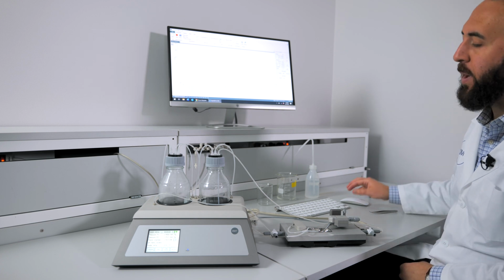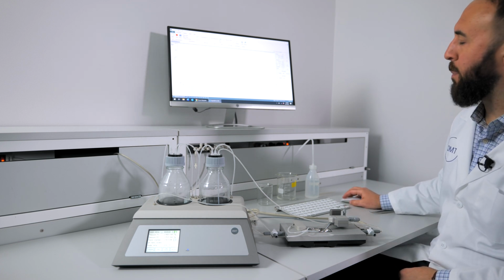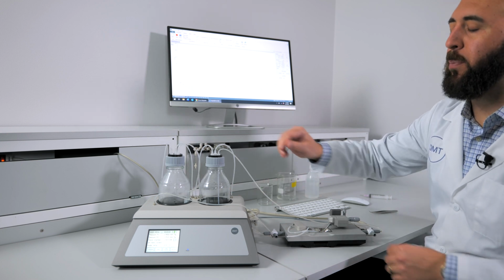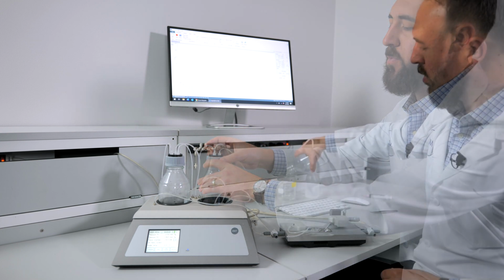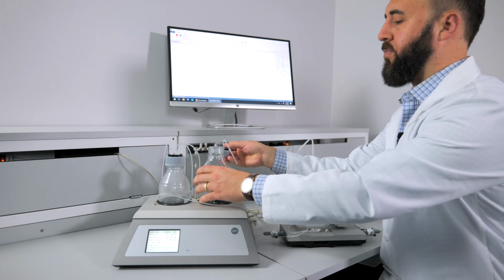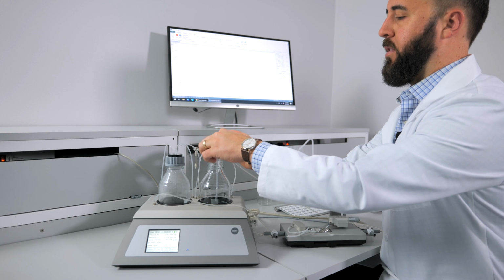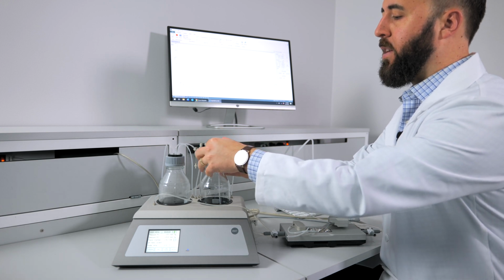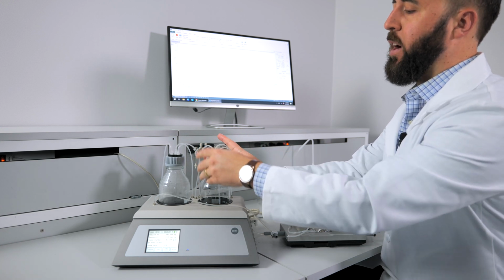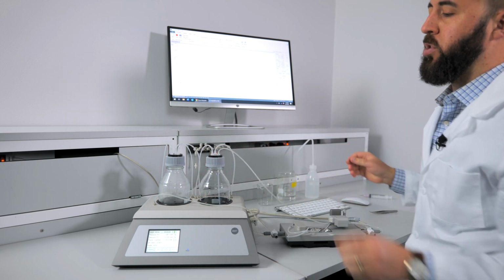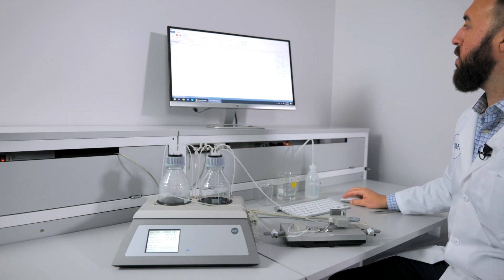After 15 or 20 minutes have passed, you can stop the pressure and empty the P1 bottle of the distilled water. You can reattach the bottle with nothing in it and we will repeat the process of pushing air through the lines to ensure that no buffer or water remains in the lines. Turn on pressure and make sure it reaches 150 and 70. You will let this run until the lines are dry.